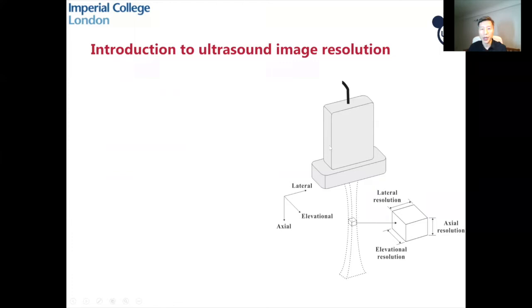In ultrasound imaging, we have a transducer and we can transmit a pulse, receive the echo, and form an image. With the resolution cell, it has actually three directions: the lateral, the axial, and the elevational direction. The resolution exists in all three directions.